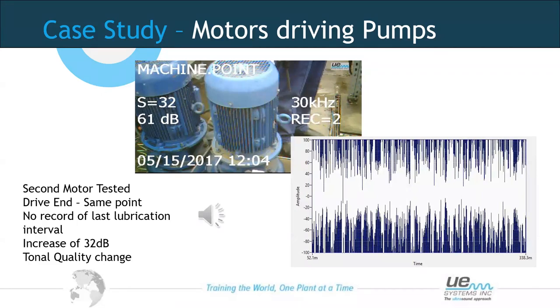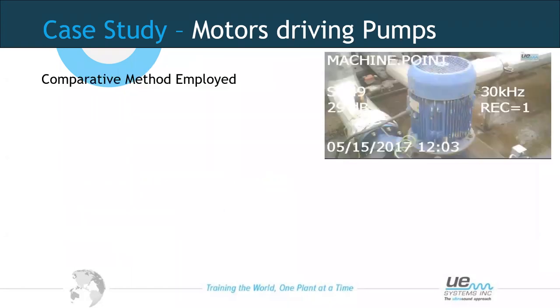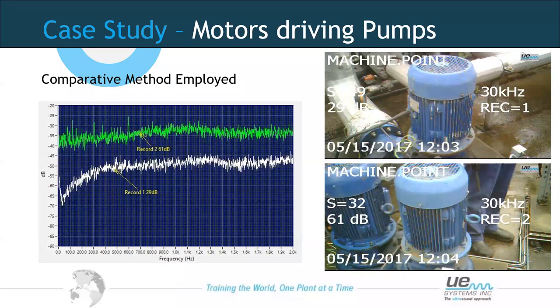The sound recording showed a clear change in tonal quality and a rise in decibel value — two like-for-like motors measured at the same point showing a marked difference. Using the FFT for comparison, the white trace versus the green trace showed a clear difference in decibel values. A couple of weeks later, the motor was taken out of service and the bearing inside was found to have totally corroded away — a confirmed failure. A good find.